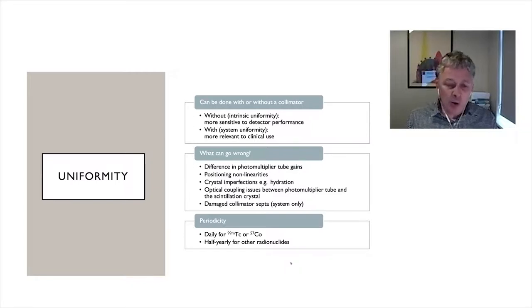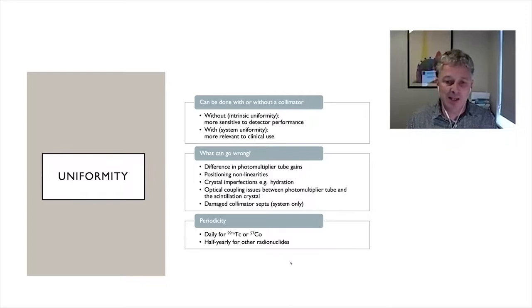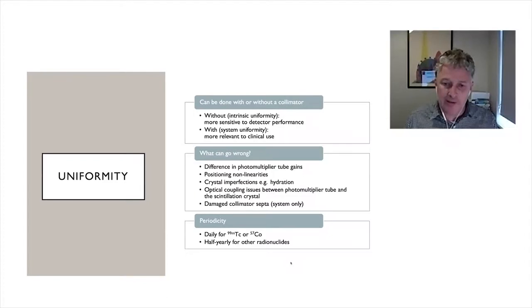For other radionuclides like iodine-131 or iodine-123, it depends on your system stability, but generally half-yearly for radionuclides other than technetium-99m is probably appropriate.